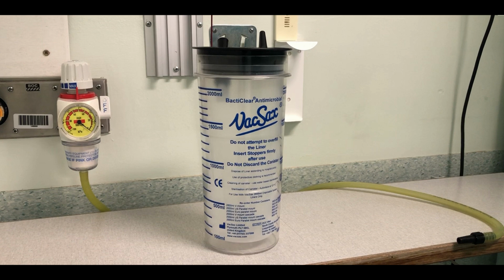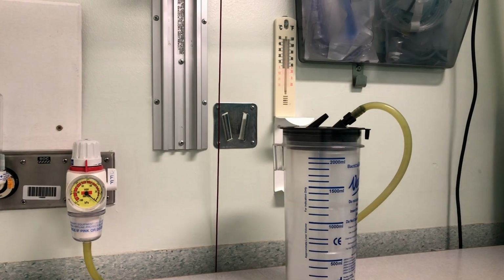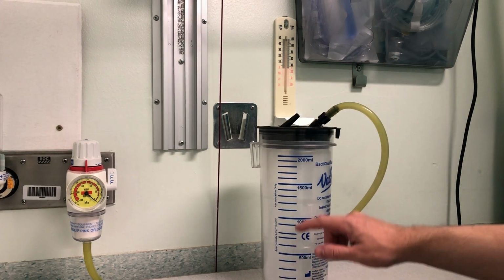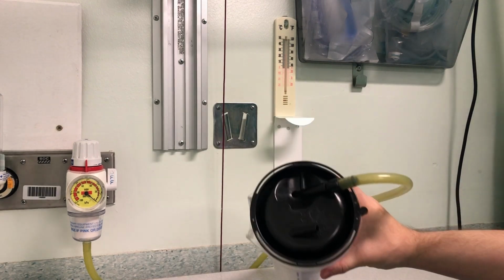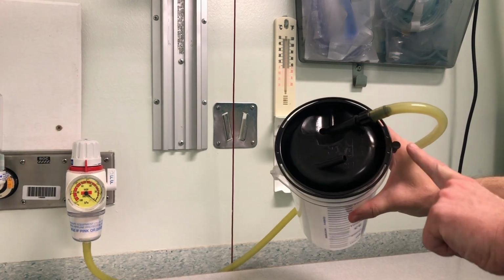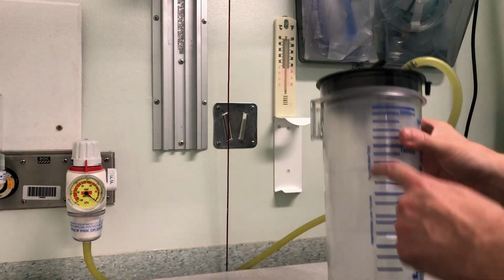Suction canisters are rigid canisters for use with appropriately sized Vacsax Bacti-Clear antimicrobial disposable suction liners, designed to minimize the risk of cross-infection. The suction canister and liner provide a temporary storage container for secretions or fluids removed from the body. These fluids or secretions may come from the patient's lungs, stomach, or wounds. The suction canister may be seen attached to the walls on a bracket or on a mobile stand in areas such as theatres. On the canister there are an increment measuring scale and a wall bracket slot, and on the Vacsax liner there is a patient port, a vacuum port, a stopper for the patient port, and graduations for measuring the content.